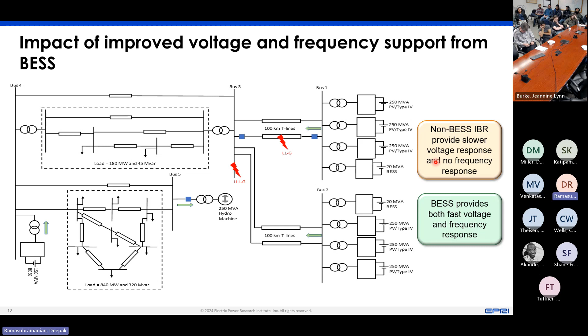And the idea was to see that if your battery energy storage system is able to provide this fast frequency and fast voltage response, and your non-battery networks provide the slower response, let's see what happens. There is a reason why we chose only the battery to be able to provide this, because there's a dispatchability aspect that you can leverage. There is a stiffer DC bus that you can leverage. There is better voltage control, energy requirements, and so on that the battery energy storage system will help provide, which the non-battery energy system network will not be able to provide, because you can't really dispatch it at a lower requirement. You can't really make use of the fact of obtaining headroom or anything like that.